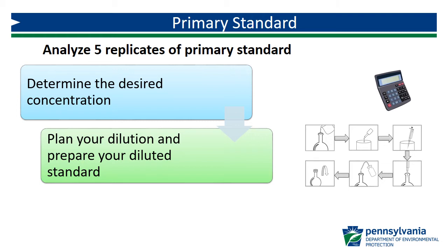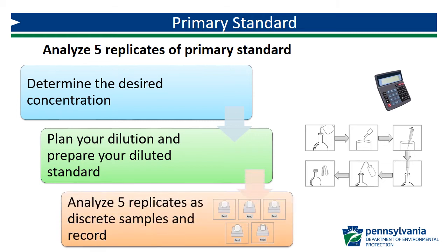You need to prepare enough diluted standard so that you can analyze five replicates, plus a little extra for rinsing the sample cell in between. The calculation to determine your dilution was covered in the video on standards. Please refer to that video if you are not sure how to dilute your primary standard. Once you have prepared your standard, you can analyze five replicates as discrete samples and record your results.